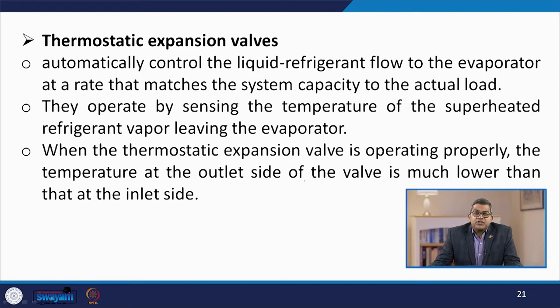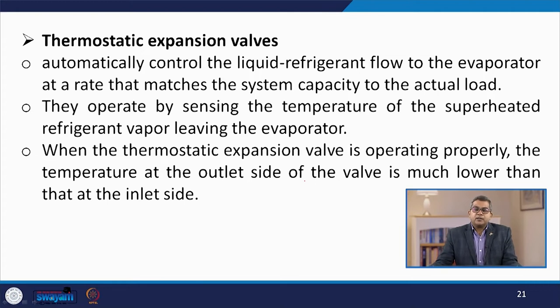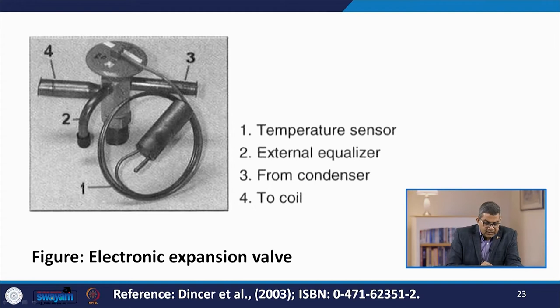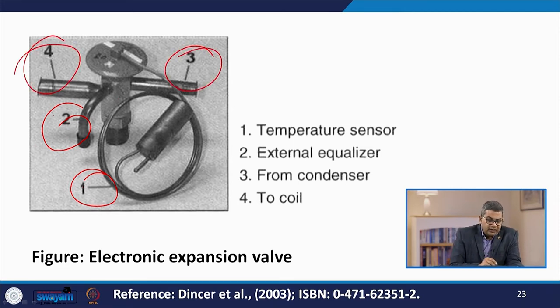Let us talk about thermostatic expansion valves. They are basically automatic type, automatically controlling the liquid refrigerant flow to the evaporator at a rate that matches the system capacity to the actual load. They operate by sensing the temperature of superheated refrigerant vapor leaving the evaporator. When the thermostatic expansion valve is operating properly, the temperature at the outlet side of the valve is much lower than at the inlet side. If this temperature difference does not exist when the system is in operation, the valve seat is probably dirty and clogged with foreign matter. Here you see an electronic expansion valve with the temperature sensor and external equalizer; the inlet line comes from the condenser and this line goes to the coil.